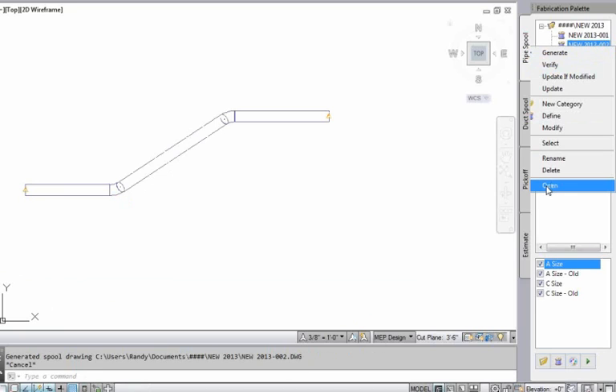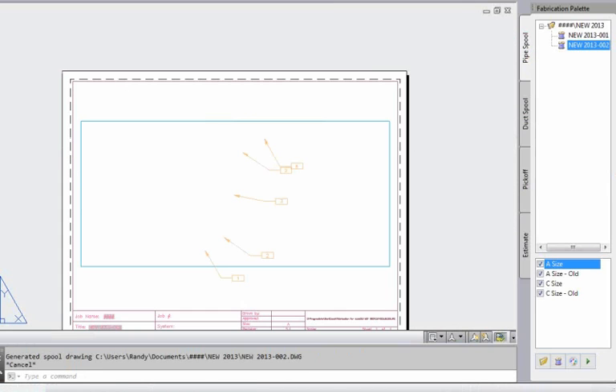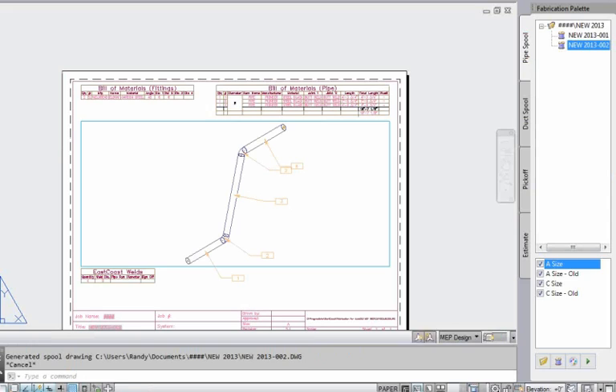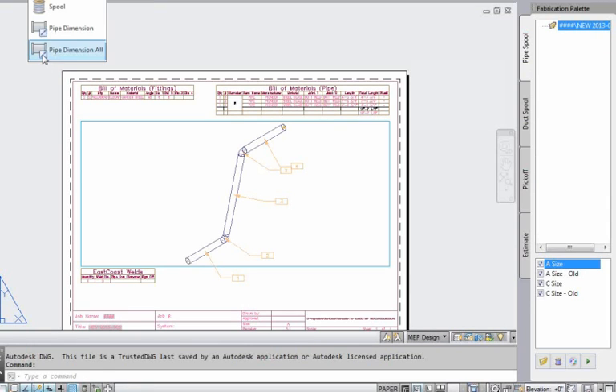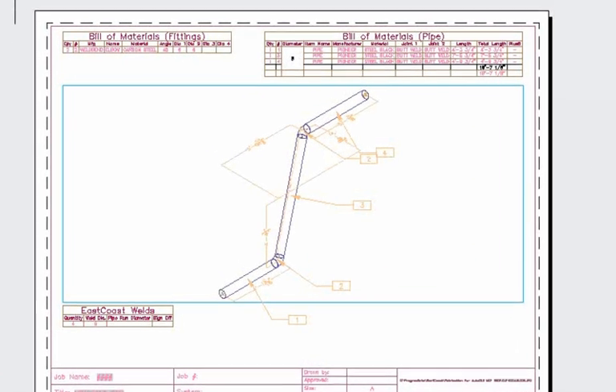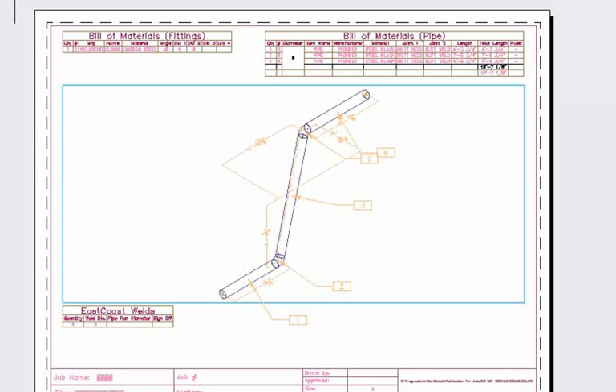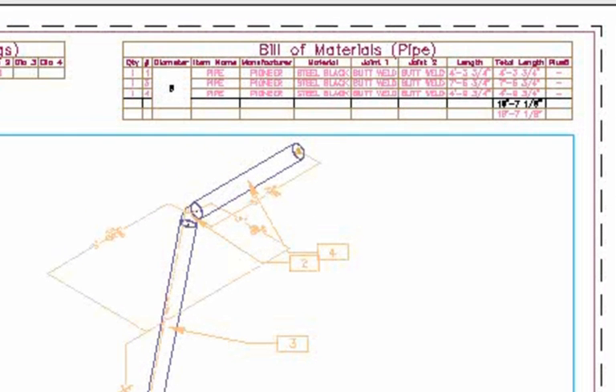Now we'll open this one up and apply the automatic dimensions. If we come back and say we want to dimension, pipe dimension all, it now adds our dimension cubes to give us our advance, our rise, and our offset for compound rolled offsets. Big improvement in tagging dimensions onto spools.